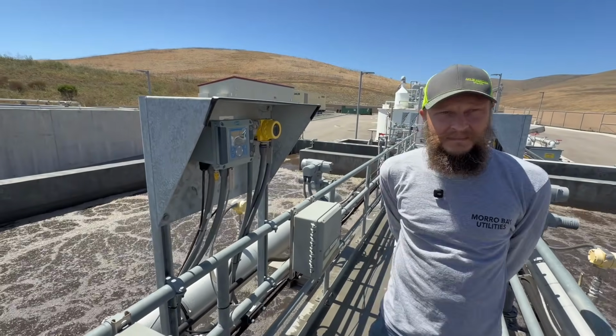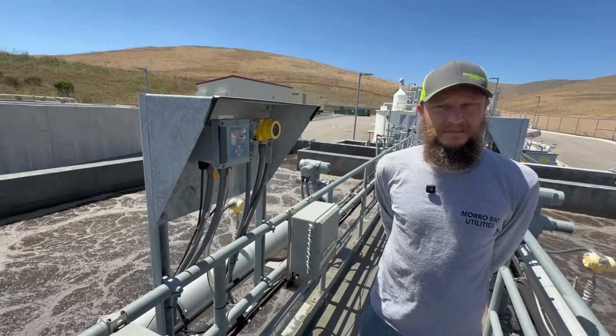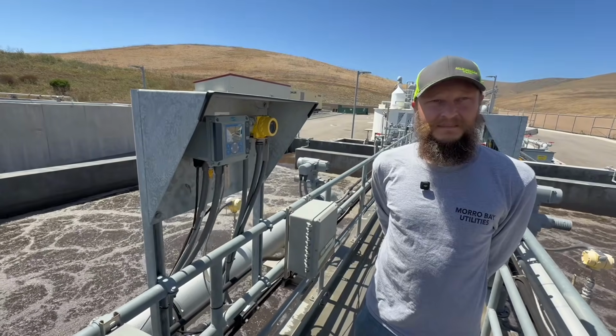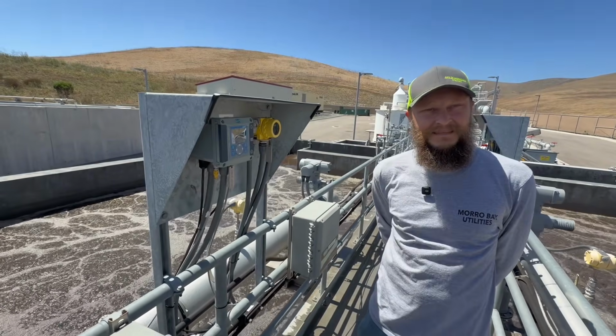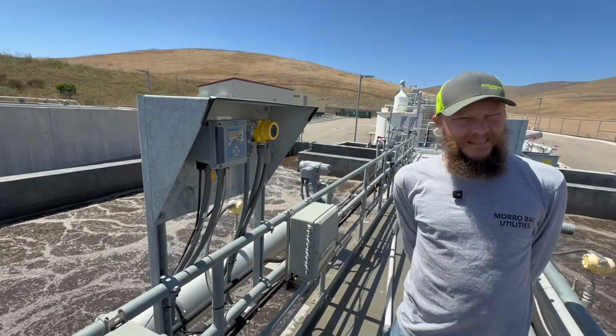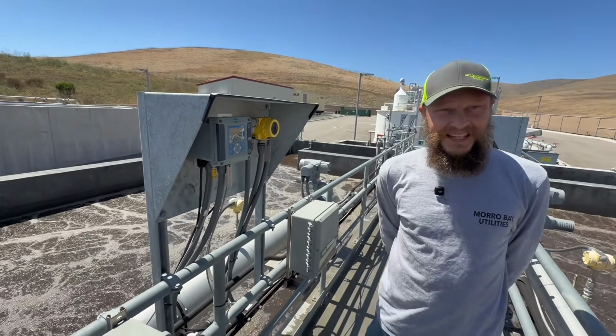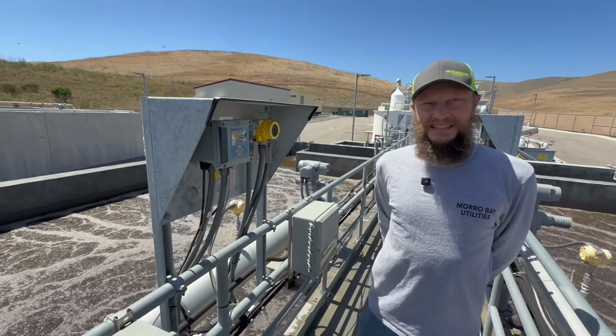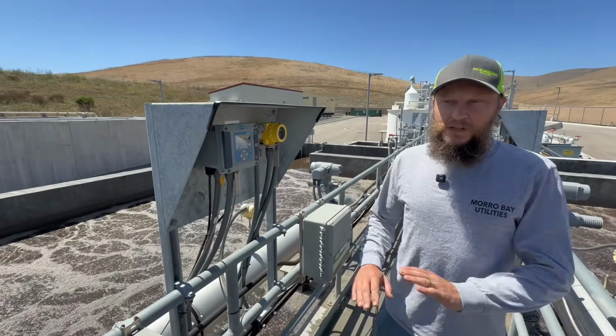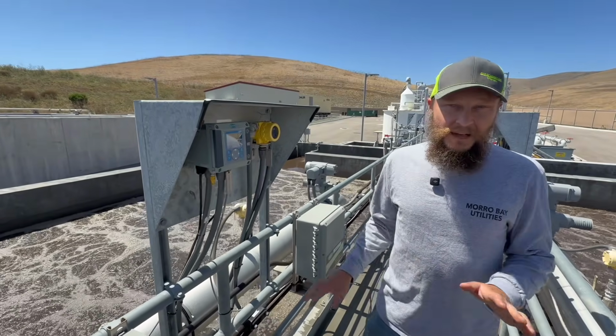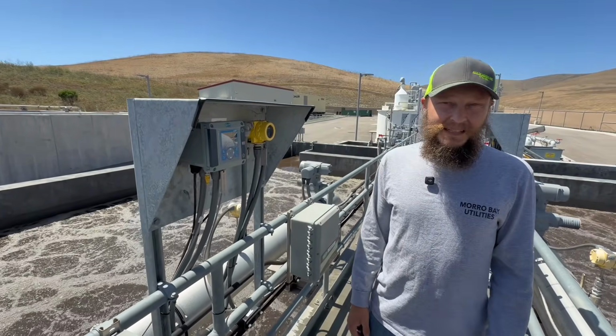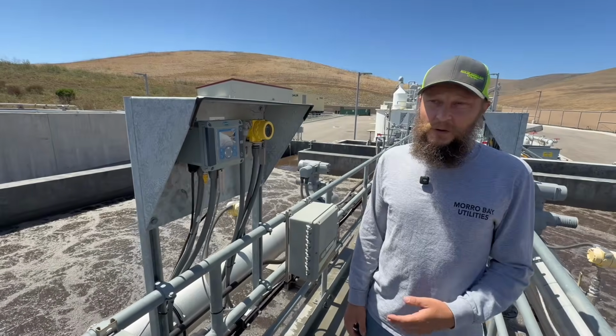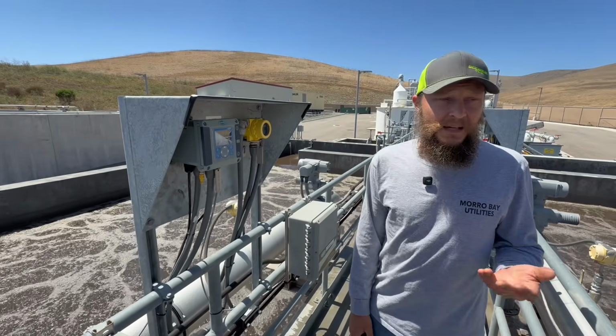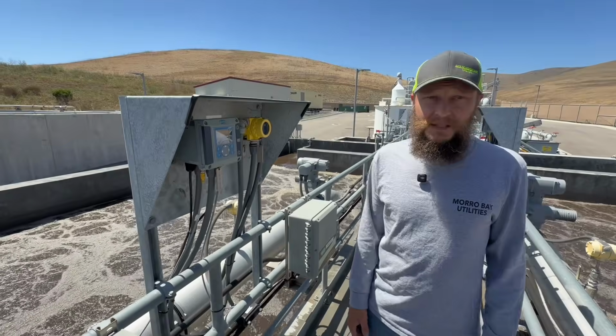One of my favorite stories to tell about 4 to 20 milliamp is when I lost my pH sensor in aeration. I got a high pH alarm, and I logged on, and my pH was 14.9, and I immediately knew the sensor was dead because there's no such thing as a 14.9 pH. Yeah. And it's scaled out to 20 milliamps, and it just died. For sure. And 4 to 20 milliamp is everywhere because it's a very robust signal, and it can travel over huge distances without degrading.